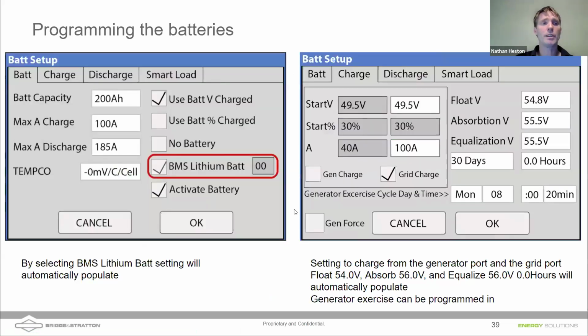I don't have time to cover everything. In the battery setup tab, if you are using communicating batteries, you want to check this BMS lithium battery checkbox there. Once you do that, it will automatically populate the majority of your battery settings. I want to point out that when you're using a Sol-Ark, it does not save any of your settings until you click OK. So if you make a change, you have to click OK before that information is actually saved. So don't just continue on and then cancel out and think that your settings have automatically saved.